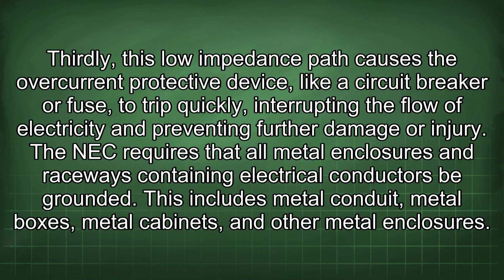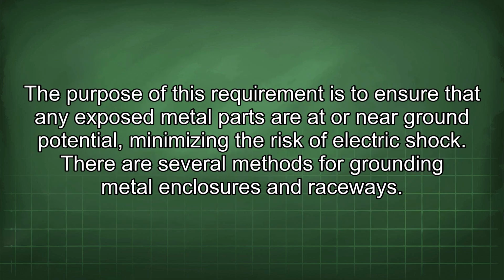Thirdly, this low impedance path causes the overcurrent protective device, like a circuit breaker or fuse, to trip quickly, interrupting the flow of electricity and preventing further damage or injury. The NEC requires that all metal enclosures and raceways containing electrical conductors be grounded. This includes metal conduit, metal boxes, metal cabinets, and other metal enclosures. The purpose of this requirement is to ensure that any exposed metal parts are at or near ground potential, minimizing the risk of electric shock.